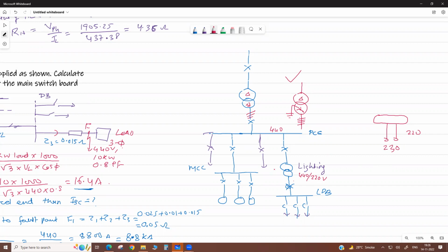Second, there is a percentage impedance of this also, like 10%. So see, if we check here, what is the fault level here? Maybe in the main distribution it is like 50 kA short circuit. But in the lighting circuit only 10 kA. Because you know these are MCBs, na. You have a lighting MCB like 5 ampere, 6 ampere, 10 ampere. Okay, this is the rated current. But the short circuit rating is also written, like 10k.